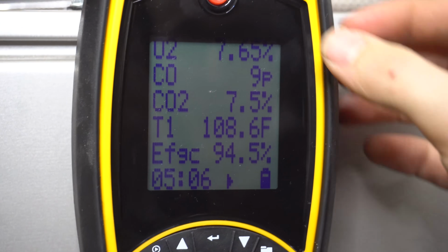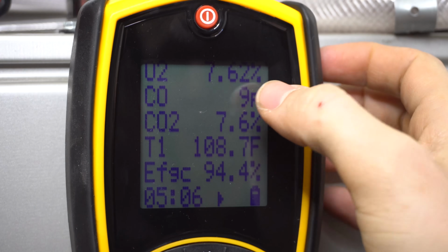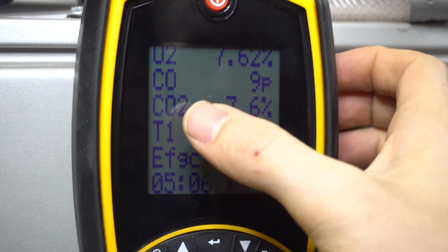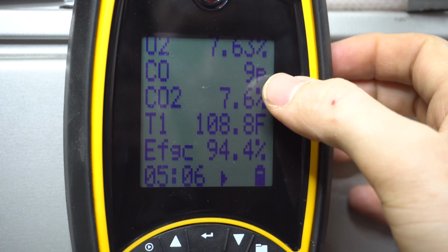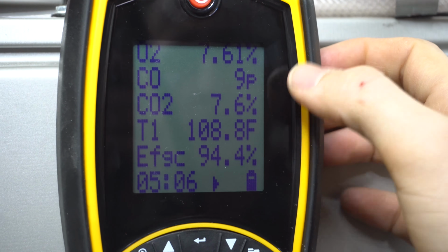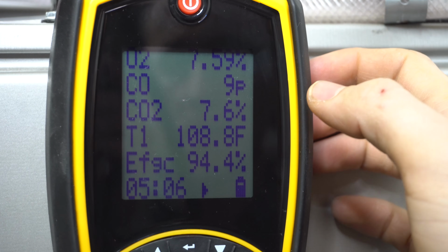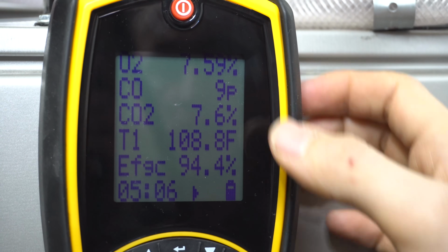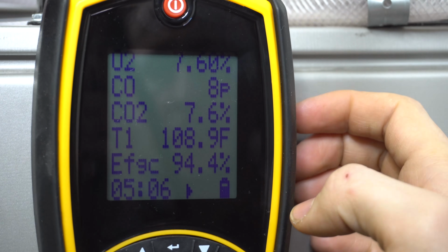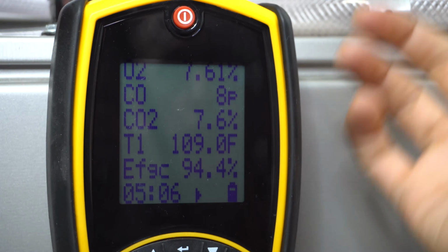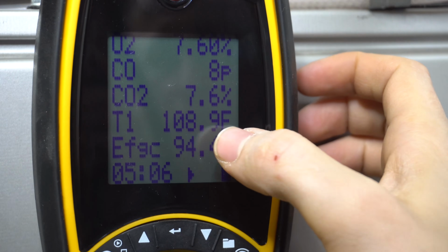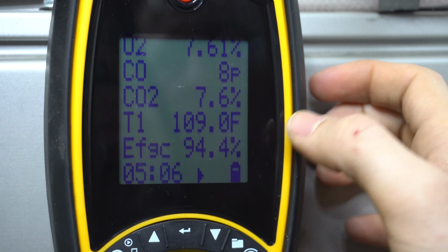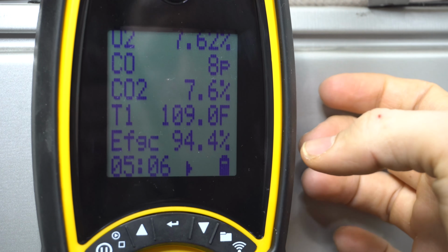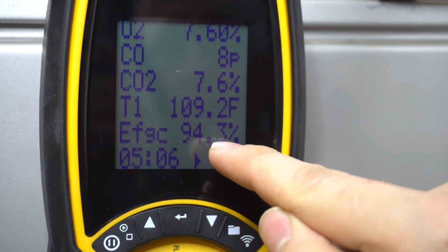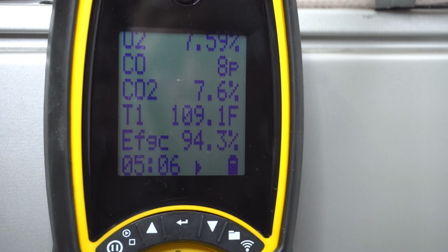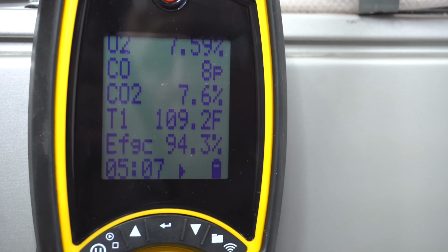So it's been a couple of minutes and the numbers are fairly stable now. Oxygen went down to 7.62. Surprisingly, the carbon monoxide actually went down to 9 parts per million, which is unusual. Typically the carbon monoxide goes up a little bit, not down. But that's good. 9 parts per million in high stage, that's very good. Carbon dioxide, 7.6%, that's normal. And the stack, or I guess in our case the exhaust pipe, the temperature inside of that went up to 109 degrees. So about 10 degrees higher, which also is normal. And our efficiency ended up at about 94%. So that is a normal read for a high efficiency furnace on high stage.